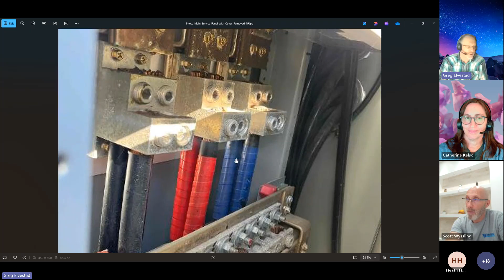Fantastic opportunity to connect on this one here with very little intrusion. Still have to shut it down with the help of the power company, but that gives us a good idea where we can connect. And finally, a shot here from the other side, again seeing what is available for installation. A fuse disconnect could live right here next to the meter set, just around the corner, and still be within our 10-foot limitation for conductor distance on the supply tap.